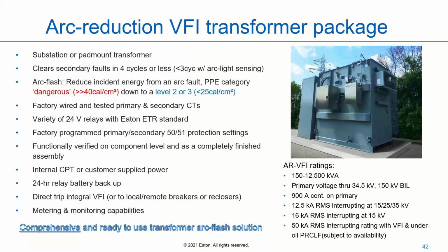And then there are the integrated features and benefits of this product that we talked about here. The big thing we want to drive home is that there are different ways to do arc flash safety on the low voltage side of your transformer, down to your low voltage breaker. But a lot of those solutions require multiple pieces of equipment, typically spread out amongst different pieces of equipment, coordinated by different groups, installed, tested, and programmed in the field. Taking all of those different pieces and standardizing them into one product that's tested and verified from the plant is the real benefit of the ARVFI transformer.